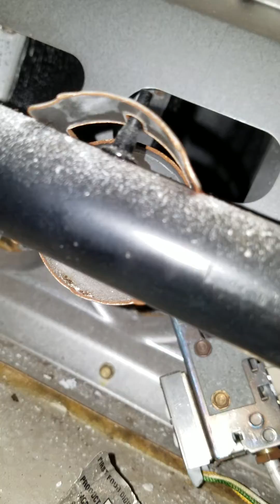Mine's an older furnace, it all varies, but after it heats up, then it's going to tell the board that there is flame present. And then the board is going to go through the safeties, check your high limits and all that good stuff and your rollouts, and then it'll send power to the gas valve. You guys heard that click.